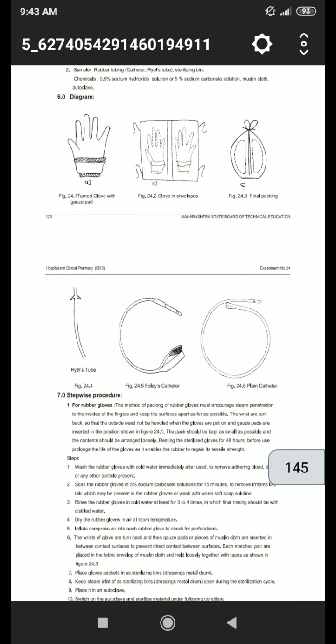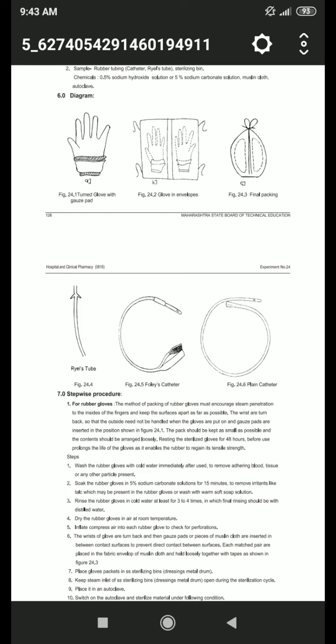Then stepwise procedure for rubber gloves. The method of packing: the packing of rubber gloves must encourage steam penetration to the inside of the fingers and keep the surfaces apart as far as possible. Then the wrists are turned back so that the outside need not be handled when the gloves are put on, and gauze pads are inserted in the position shown in figure 24.1. Okay, now you can see the first diagram. The pack should be kept as small as possible, and the contents should be arranged loosely. Resting the sterilized gloves for 48 hours before use prolongs the life of the gloves, as it enables the rubber to retain its tensile strength. Okay, these are the notes for rubber gloves.